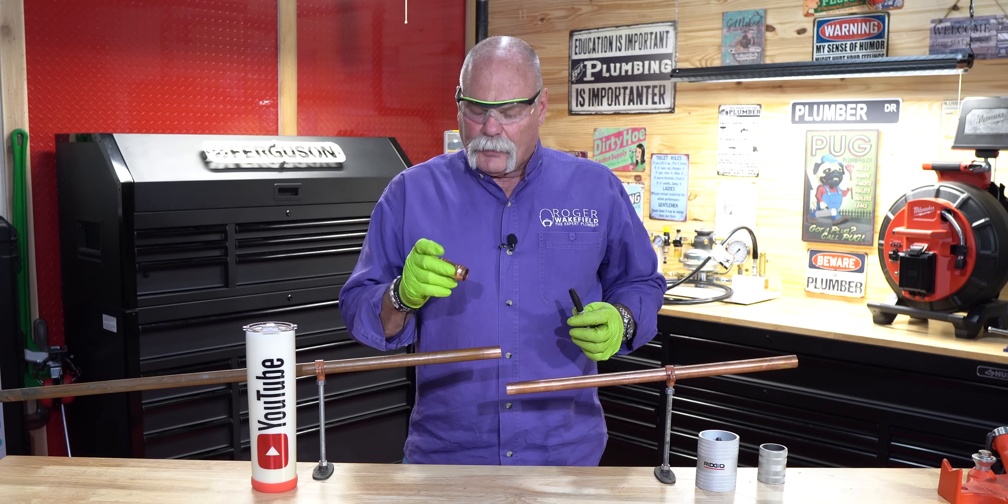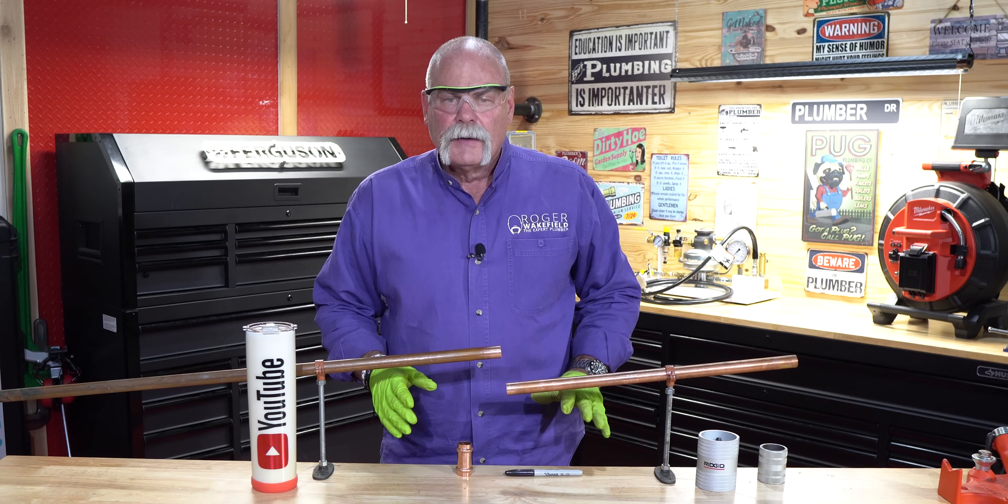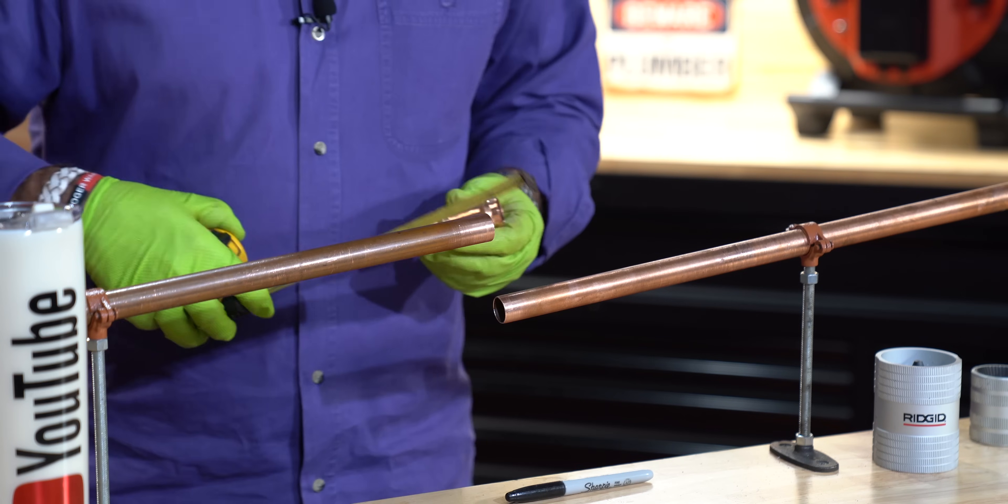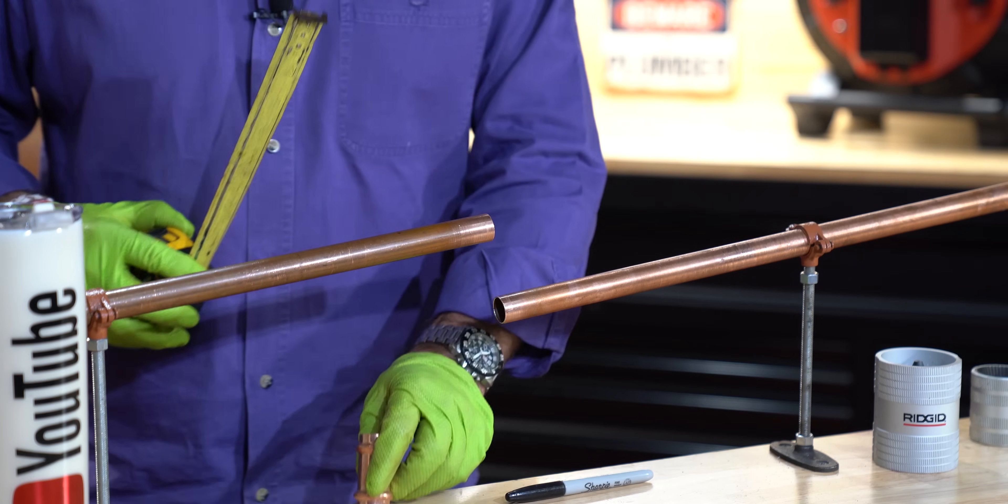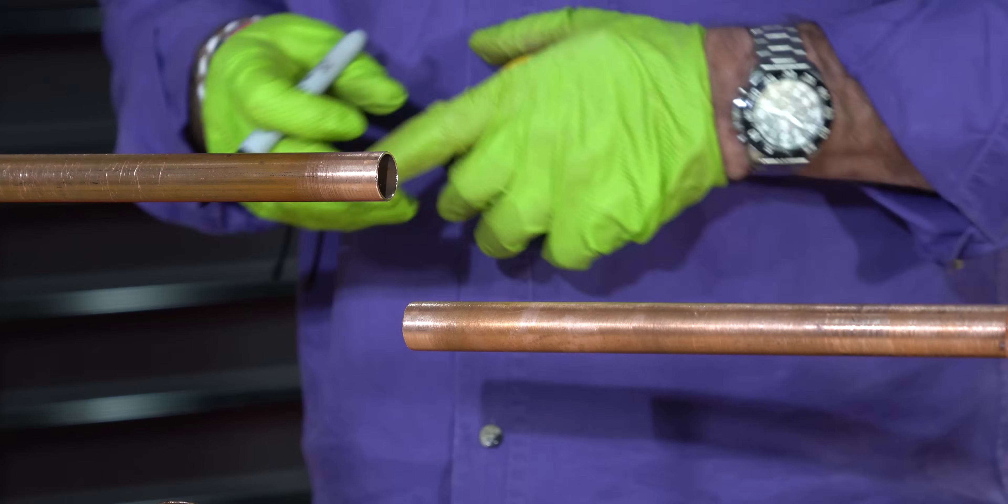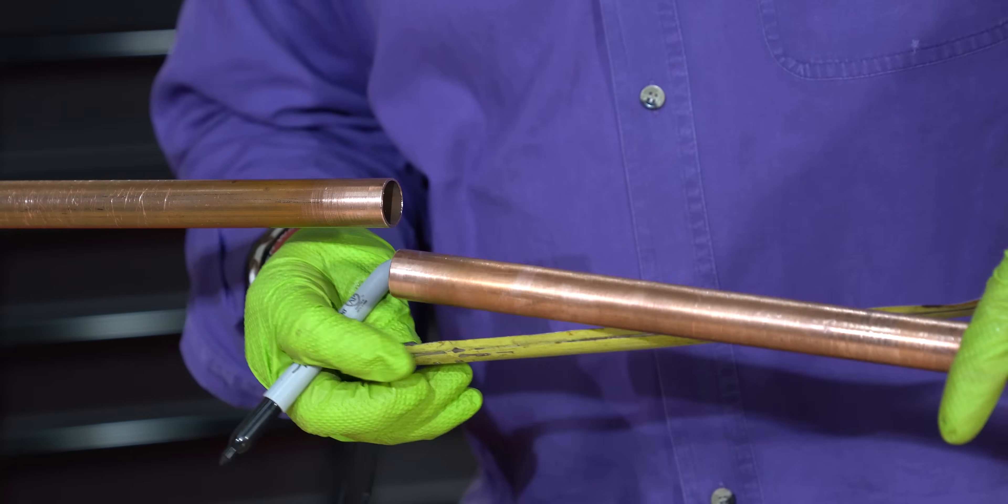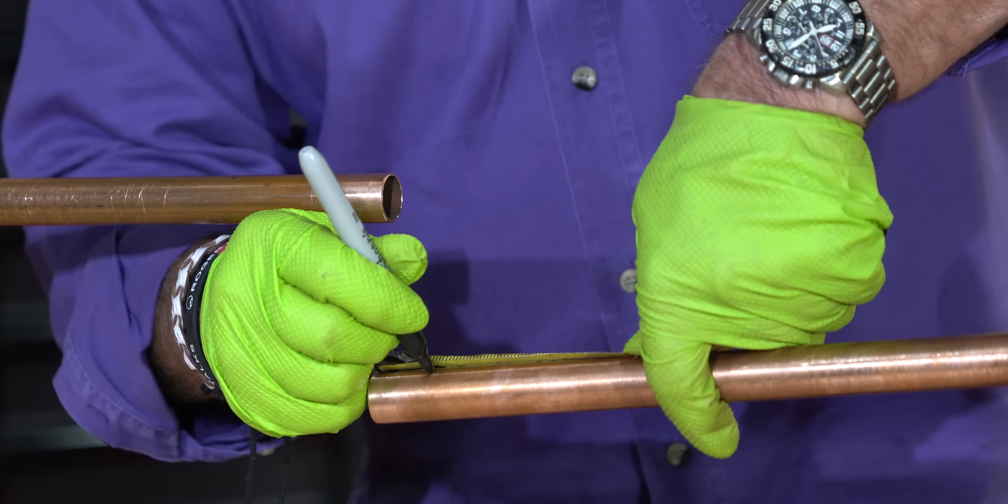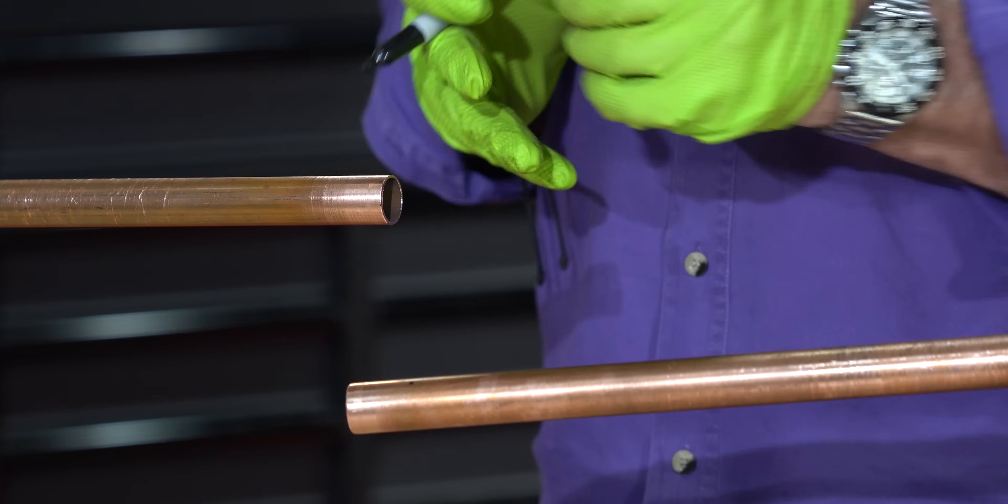So now, the press fitting is a non-stop too. I want to make sure that I get this right and I don't have any flux on the pipe. So I'm going to measure my overall length. It's two and a quarter. So I know I want to come back one and an eighth inches on each piece of pipe to make sure that I have my fitting right where it goes. So I'm going to mark one and an eighth on both sides.